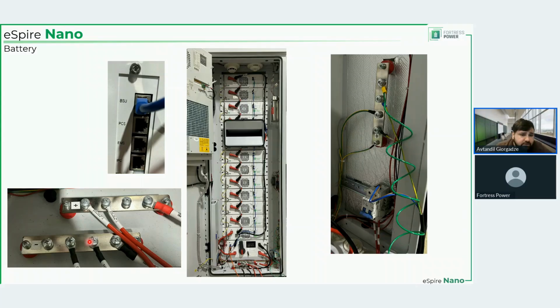As I said, 2 pluses and 2 minuses. This is the communication to the PCS. So from this port to the inverter. This is the ground. So you take this ground and connect to the ground on the inverter. And this is the AC supply for the battery cabinet. This you can connect to any phase, really. And what matters is that it should be on the backed up circuit if you are doing backup.